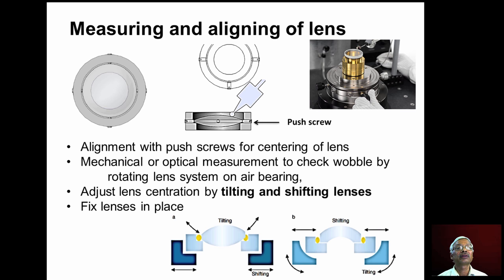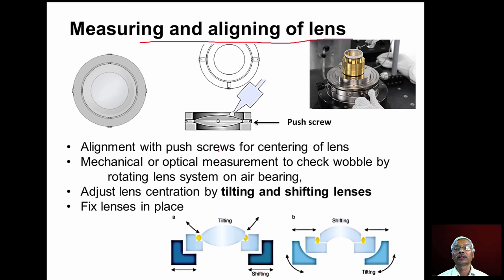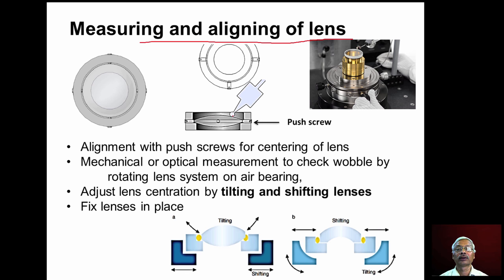Now we will discuss measuring and aligning of lenses. When different lenses are assembled in the barrel, we must align them so that the optical axis of all lenses aligns with the barrel axis to get a quality image. We can measure the alignment by rotating the lens and checking for wobble, using either a mechanical or optical measurement system.